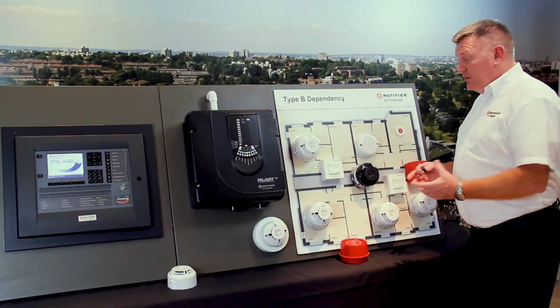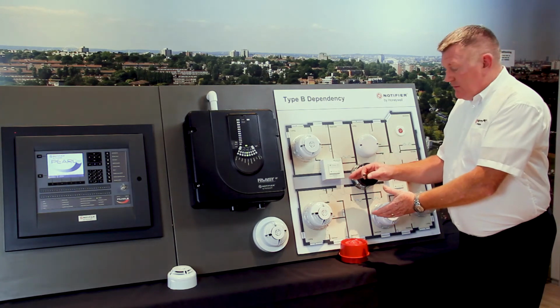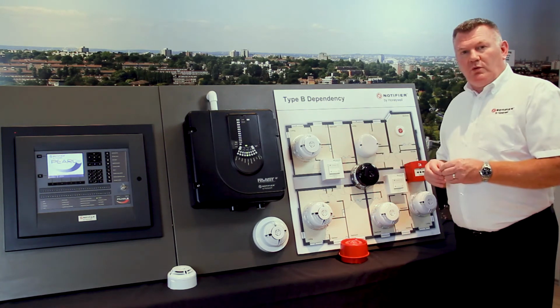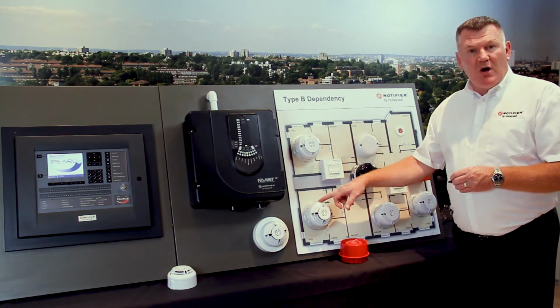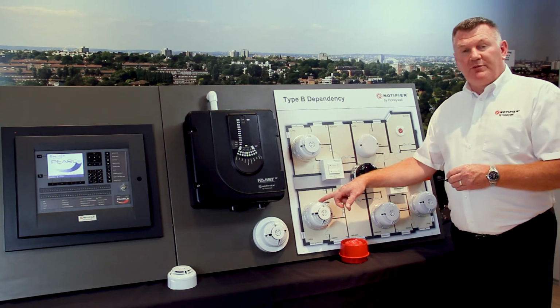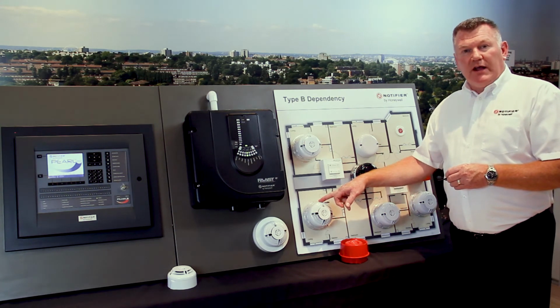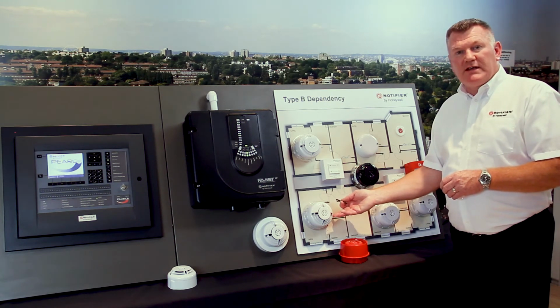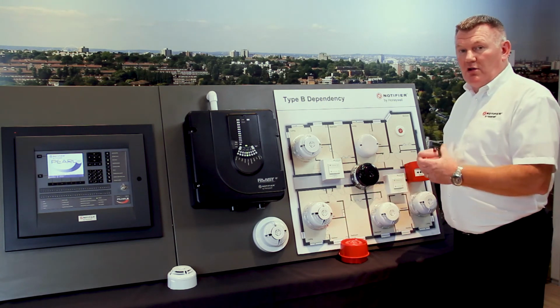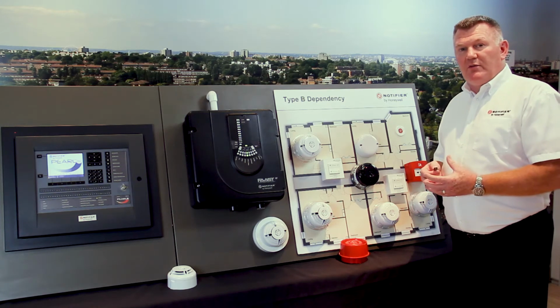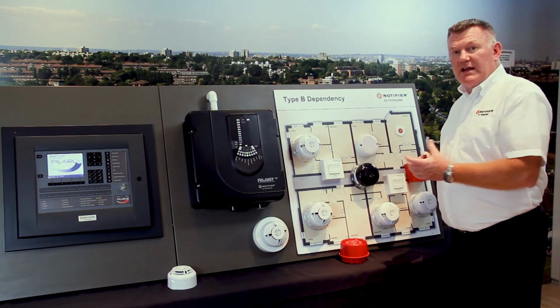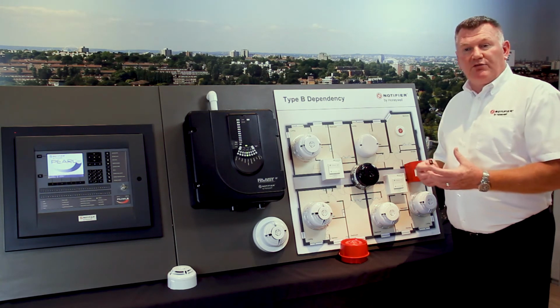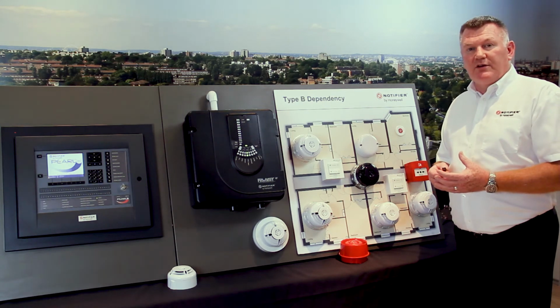So in this scenario, in flat 3, zone 3, what we want to do is use the Smart 2 detector, which is an optical with thermal, and then we can do an unconfirmed fire event from the optical detector, and then we can do a confirmed fire from the thermal detector within the same detector. This would be as if we had a genuine fire within a flat.